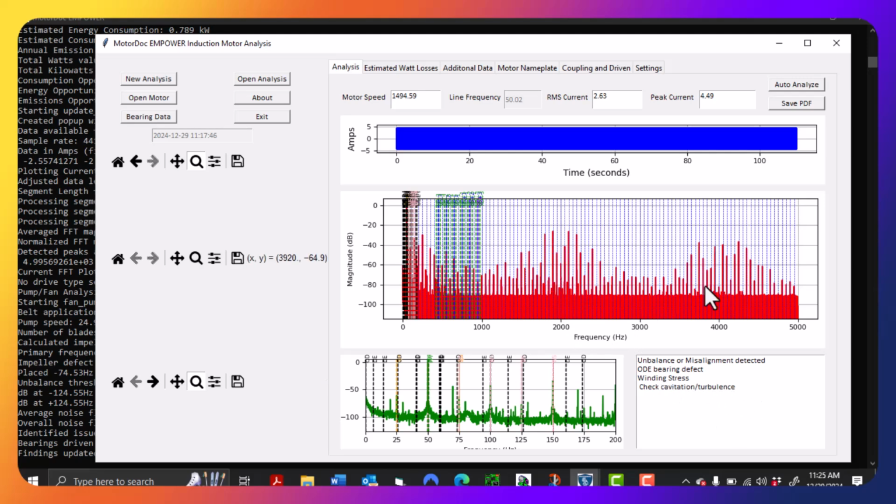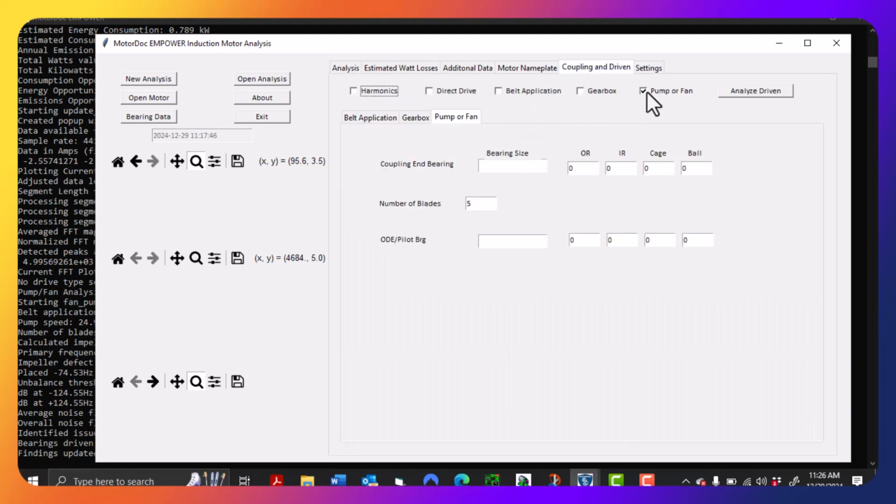Now you'll notice that there's some drive stuff here. So this is the firing frequency of the drive, and this is the second harmonic of that. Well, supraharmonics, or harmonics greater than 2 kilohertz, are a direct result of inverters and so on. And this is a new area that we're delving into. There are new standards that look at 2 kilohertz to 150 kilohertz because of the harm that it does and its ability to blow away shaft brushes and things like that and give you fluting issues even when you think you've corrected for it. So we have added in another capability.